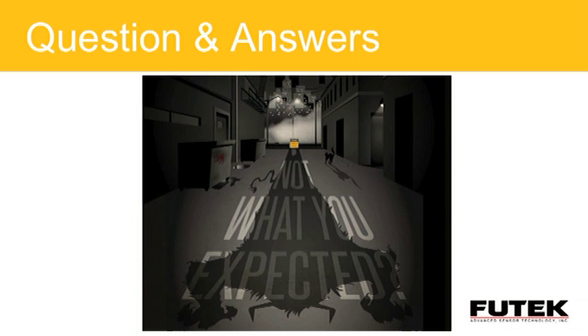That's a good closing question. On the sensor side, we take these things for granted—what is millivolt per volt? Ultimately, a standard load cell, without any additional displays, amplifiers, or electronics, provides a millivolt output. For example, if you're exciting the Wheatstone bridge of the load cell with 10 volts and getting a 20 millivolt differential output, you divide 20 millivolts by 10 volts excitation, generating a 2 millivolt per volt output.